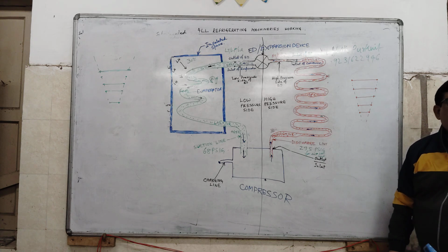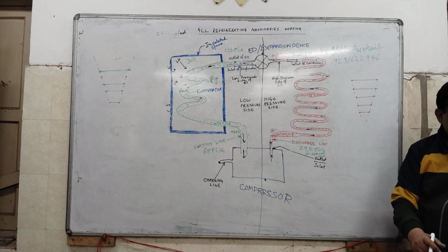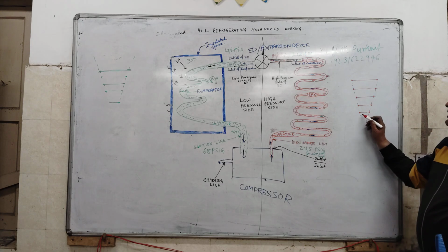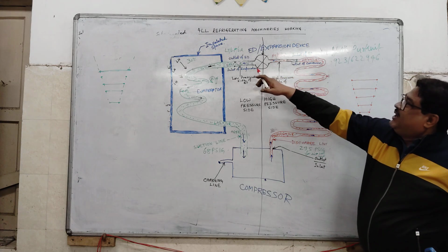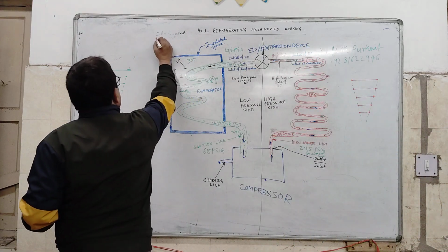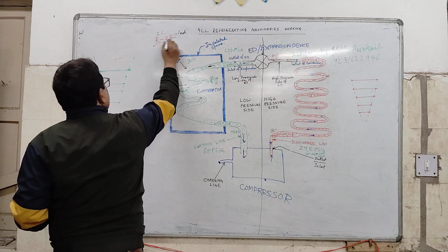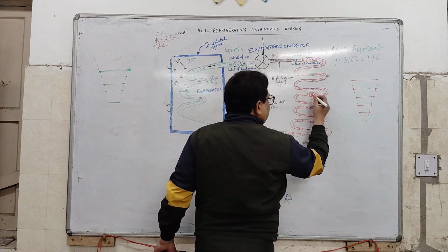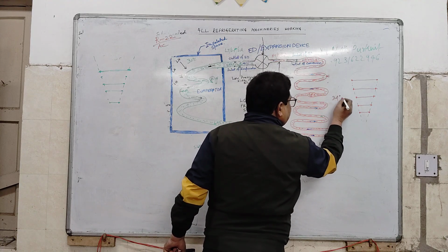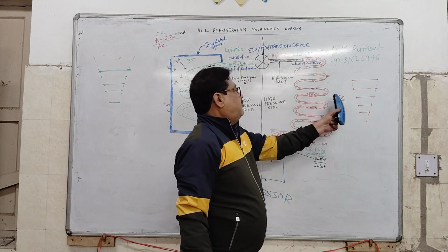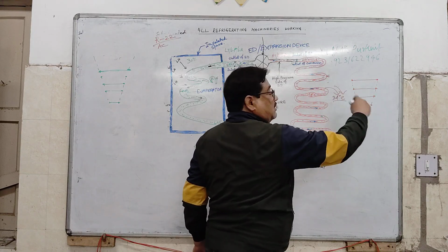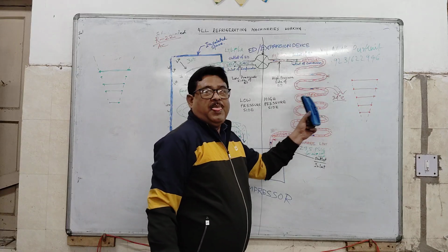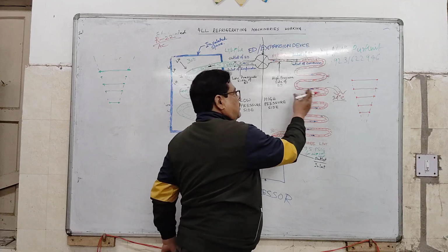And when condensation begins, latent heat should be rejected. So latent heat should be rejected from the condenser. Suppose you use R22 refrigerant, and for this machine its condensing point temperature is 54 degrees centigrade and the ambient temperature is 34 degrees centigrade, near the above average we take. So there is a 20 degree difference, so heat can be easily discarded. So heat can be rejected from 54 to 34 to the atmosphere, and due to the rejection of heat, it comes back to liquid again.